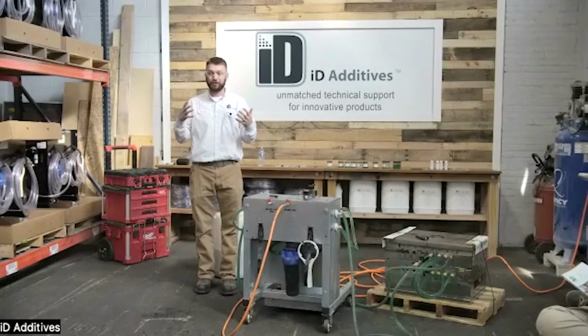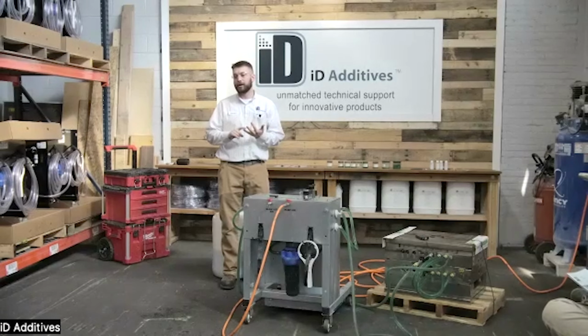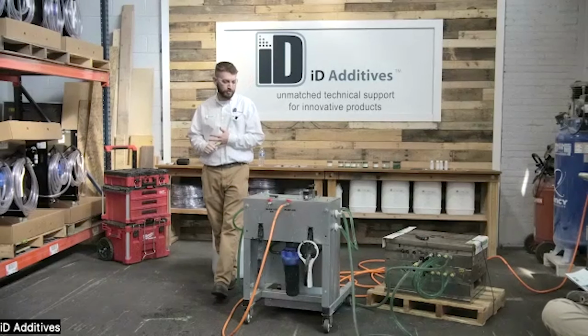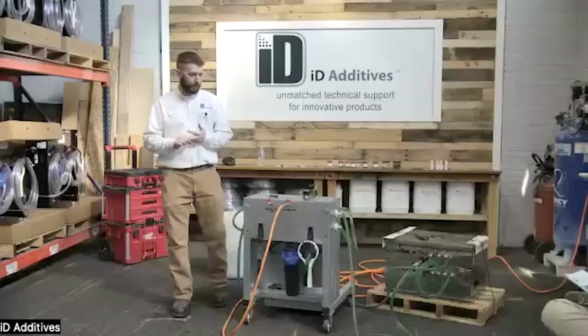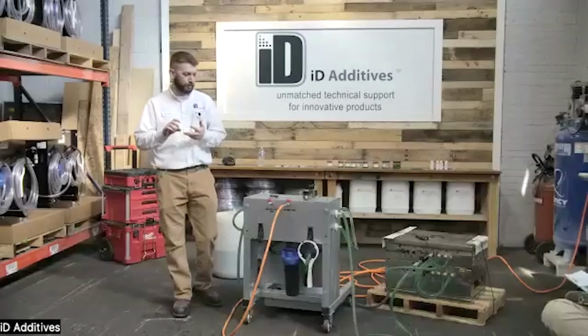Bell & Gossett and SmartFlow have great tools online where you can plug in your water temperature, glycol percentage if you're running that, and your line diameter. You'll find your delta T, and then there's a sweet spot called your Reynolds number to hit turbulent flow.